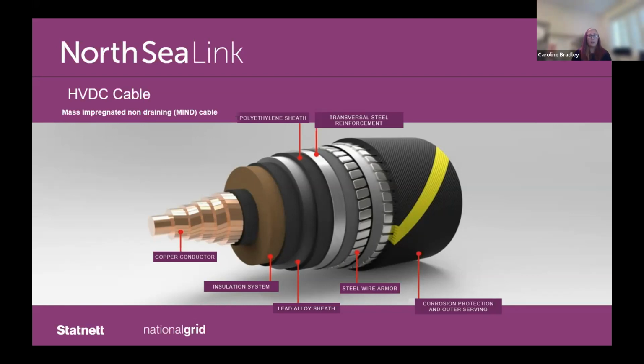We have a copper conductor with mass impregnated insulation - a lapped paper insulation impregnated with a highly viscous oil, more like the Vaseline end of the spectrum than the oil in your car. There are metallic sheaths on the outside for mechanical protection, plastic oversheaths for moisture protection, and then two layers of armor wire. The armor wire supports the cable when you hang it off the back of the boat to install it in the water. Because we were dealing with such deep water depths and such a heavy cable, two layers of armor wire were required. Then there's some yarn, which is stripy so you can see it on the seabed, to again protect the cable from the outside world. That was our design.